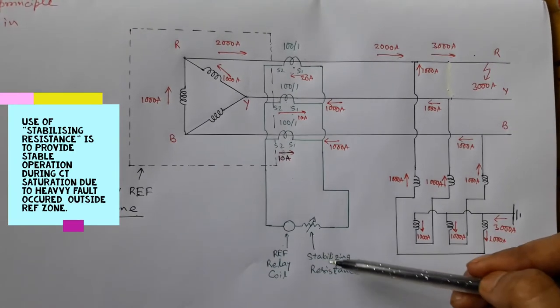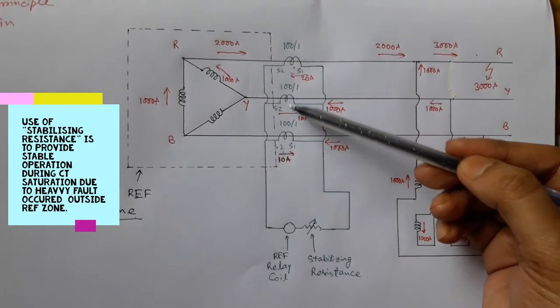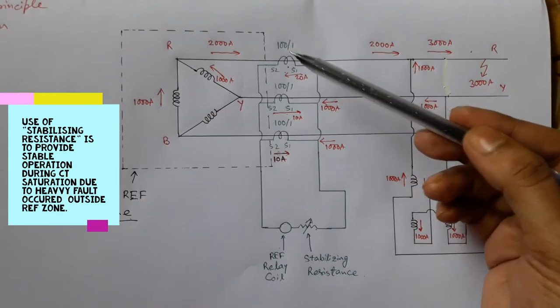In the case of high impedance restricted earth fault protection, all the CTs connected in the primary circuit should have the same CT ratio.